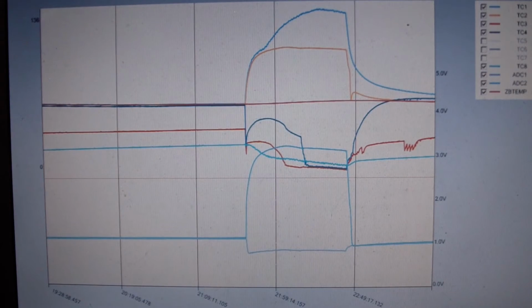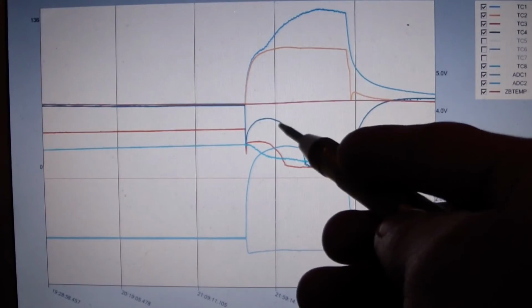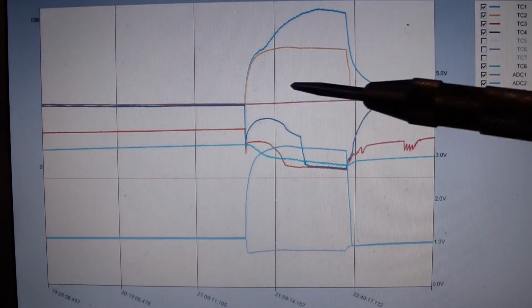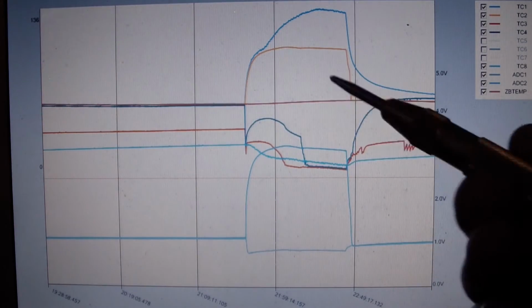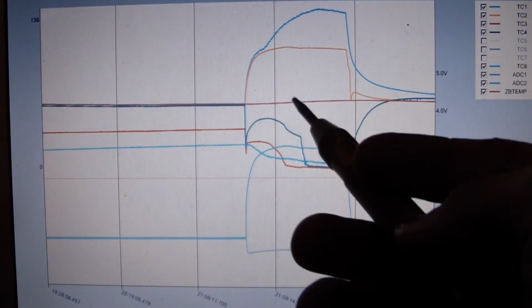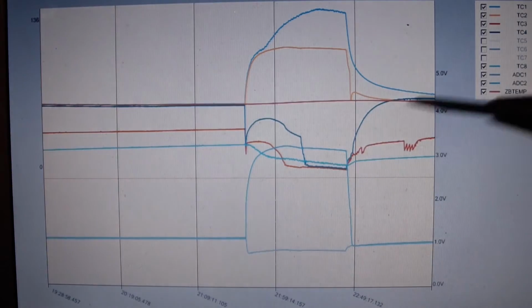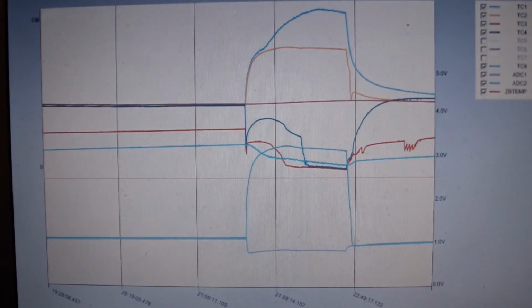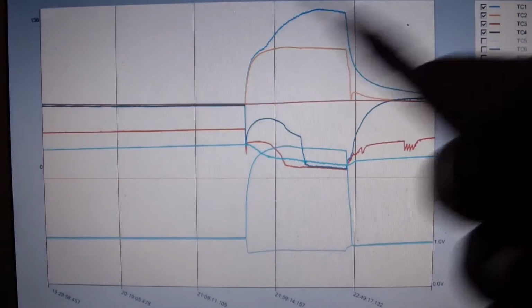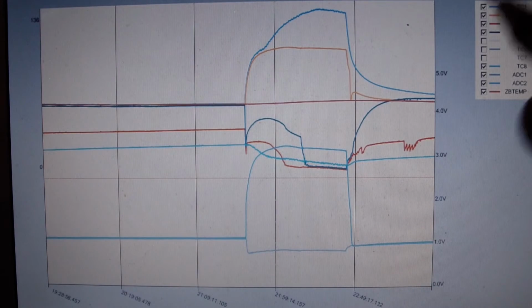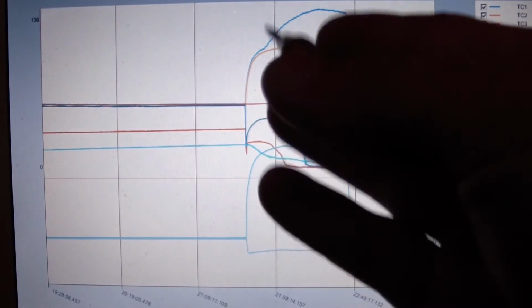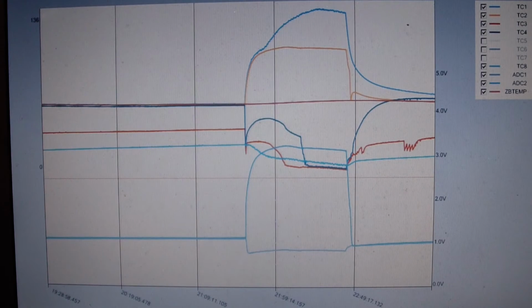Capillary tube is being cooled down, but we're actually starting to kind of get ahead of it a little bit and get a little bit less superheat on the suction line, a little less rarefied gas, more dense gas going into the suction valve, and a little bit better mass flow rate through the compressor, and then correspondingly through the cap tube as well. So I think that's an important point to point out.